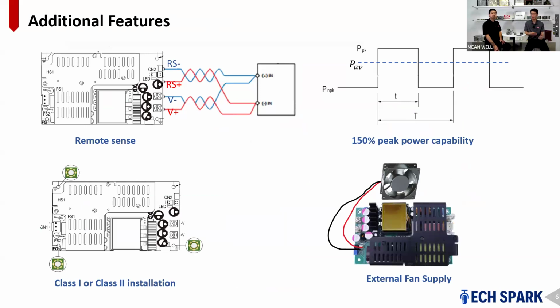One is remote sense: when voltage passes through the output cables there's some voltage drop, so the voltage at the load may differ from the voltage at the terminal of the power supply. If the application requires a precise output voltage, for example 48 volts, the power supply can sense the difference and automatically increase the output voltage at the terminal by 0.1 or 0.2 volts, so the application gets the exact voltage it requires.